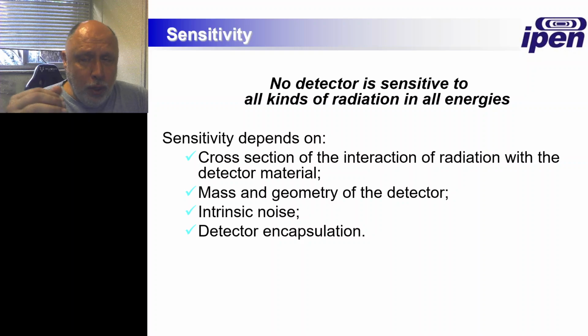So we need to know if our events will be above this threshold, this noise. Otherwise, you will miss your events in noise, right? Think about you talking to someone in a quiet room or in a very loud environment. I'm sure it has happened to you that you're talking to someone and you're not listening to half of what he's saying because the place is too crowded, too noisy, right? For detectors, it's the same. In a noisier environment, you need to talk louder. In a noisier system, you need to have larger pulses if you want to detect them, right?